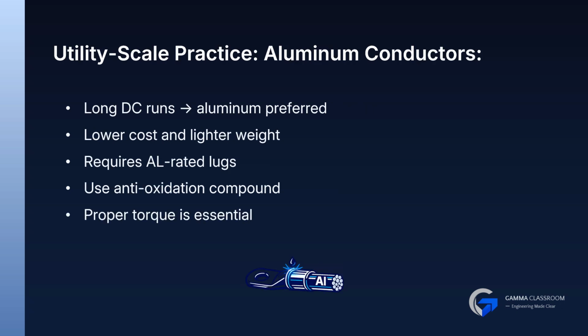In large solar farms, the home run cable can be very long, sometimes over 100 meters. Copper becomes extremely expensive at those lengths, so aluminum is used to reduce BOS cost. Aluminum requires aluminum-rated lugs, oxide inhibitor, and correct torque to ensure long-term reliability.